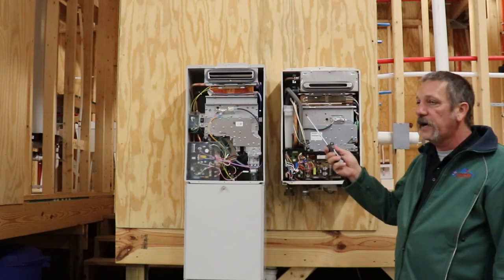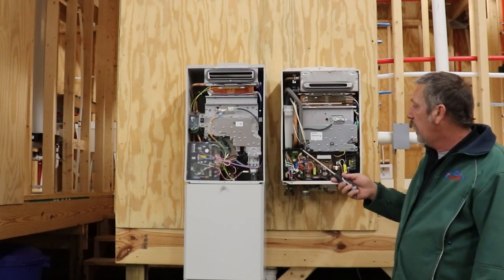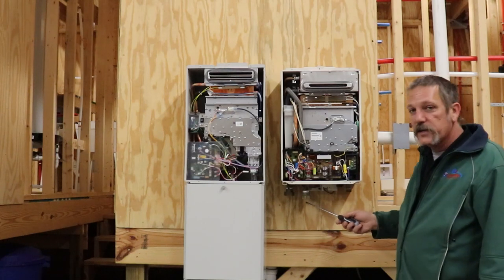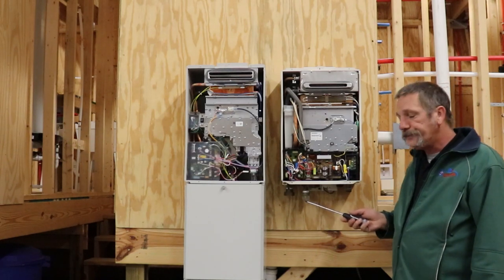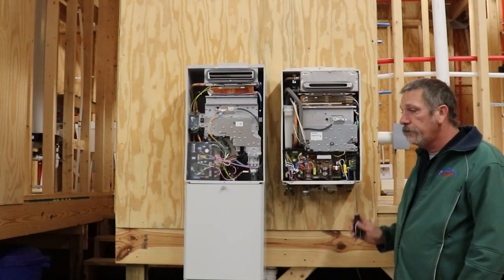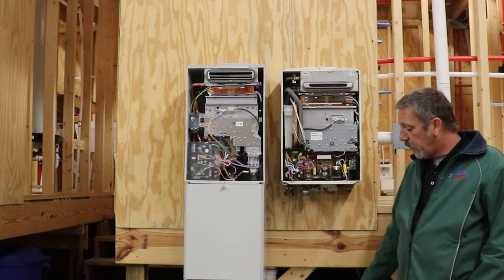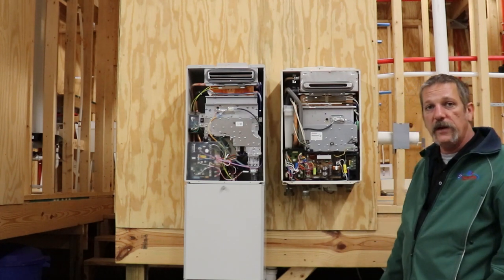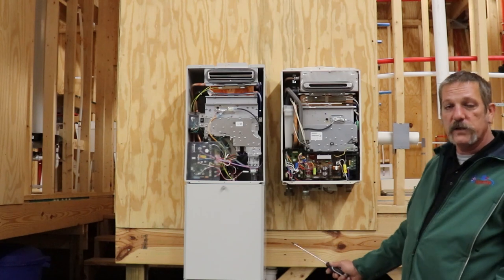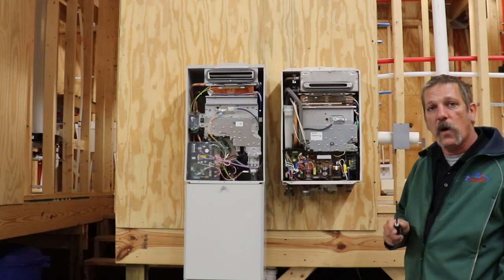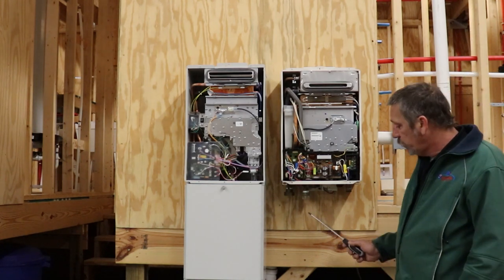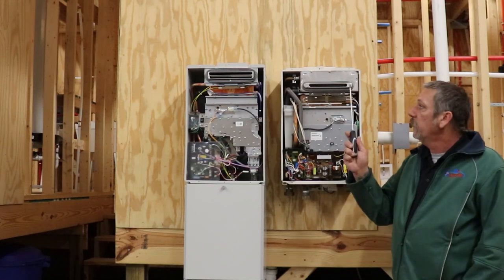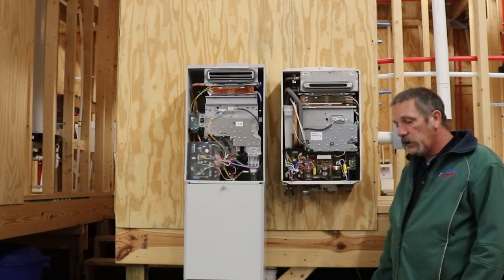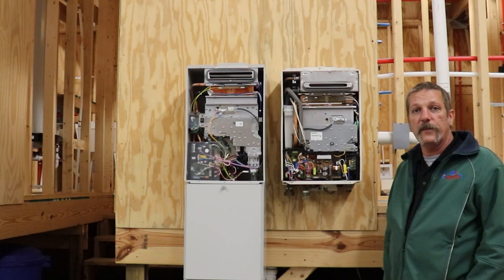It's not acidic enough to burn through anything, but then it's gonna run down and there's actually a hookup for a little tube down here. So if you've got one of these, you're gonna have two pipes hanging down at the bottom. One's for your relief and one's your condensate line. Most of the time your condensate line is smaller. It's gonna be a half inch. So when this thing is running, it's gonna build condensate and you're gonna have a little bit of water drip, drip, drip, dripping out of the bottom.